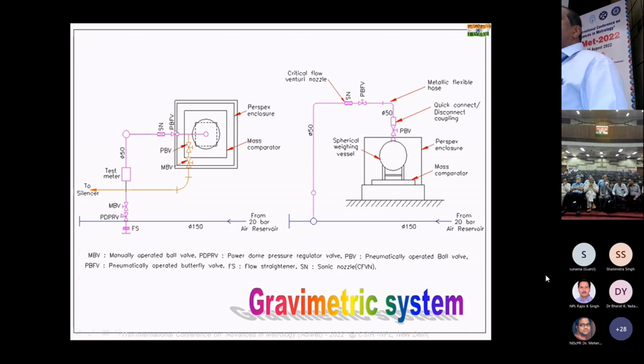And when we start the flow, it starts from zero, and it will take a delta T time to reach the steady flow. So when we directly dump the flow into the vessel, the timing starts when the flow has not reached the steady condition. So initially, the flow will be bypassed to atmosphere. And when we ensure that the flow becomes steady by looking at the pressure and conditions, it will be diverted to the vessel.